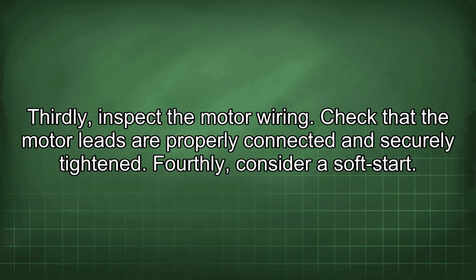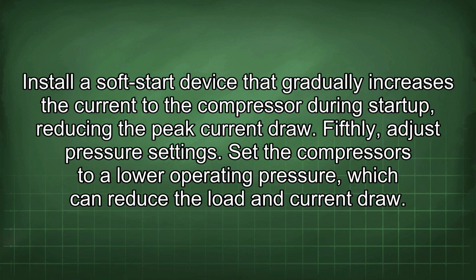Thirdly, inspect the motor wiring. Check that the motor leads are properly connected and securely tightened. Fourthly, consider a soft start. Install a soft start device that gradually increases the current to the compressor during startup, reducing the peak current draw. Fifthly, adjust pressure settings. Set the compressors to a lower operating pressure, which can reduce the load and current draw.